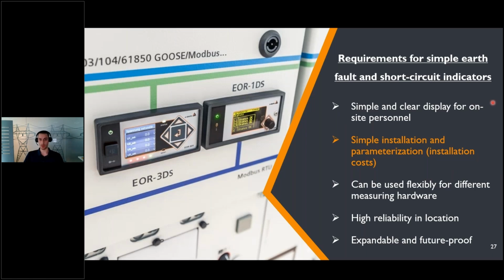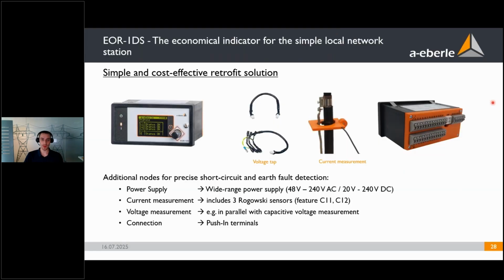Next point would be simple installation and parameterization. As mentioned before, the most simple and most cost-effective retrofit solution or installation option of the EOR-1DS would be the retrofit solution, with the current measurement via Rogowski sensors and the voltage tap. The other simple installation features of the EOR-1DS are that you have a wide range power supply of DC and AC power supply, and wide range in voltage. So that way you can install it in all of your stations and do not have to order a specific variant of the EOR-1DS for each specific station or each type of station.